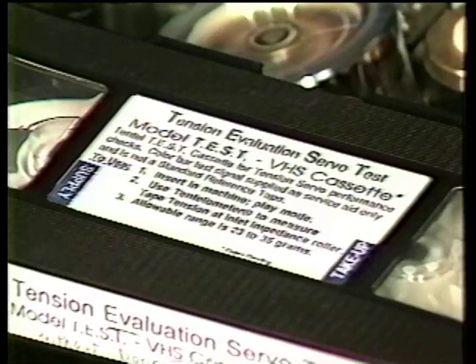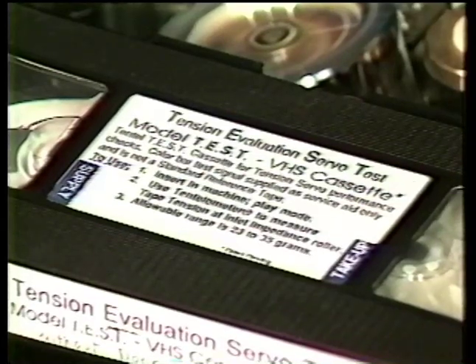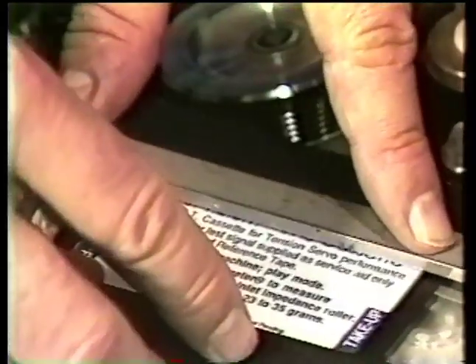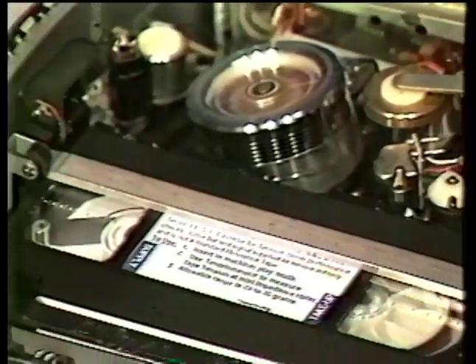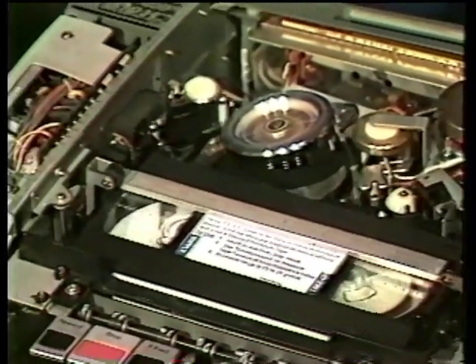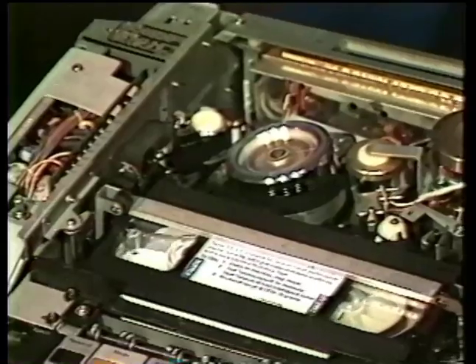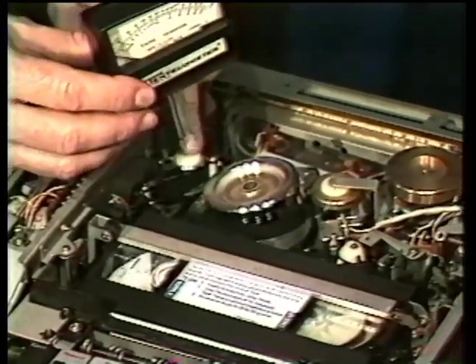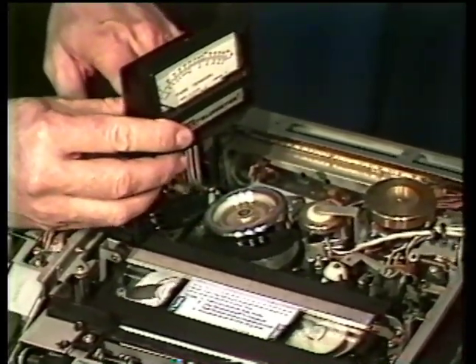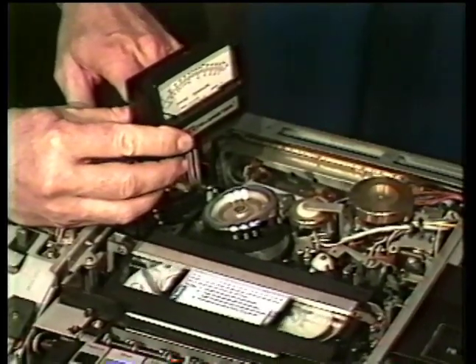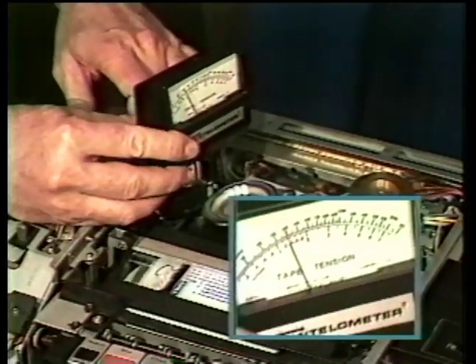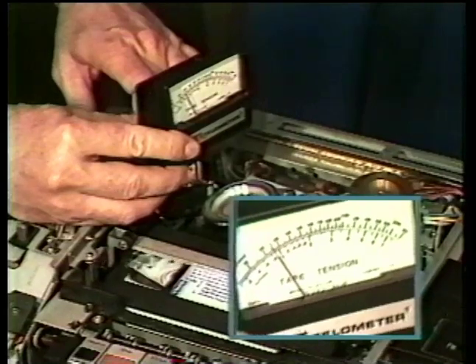Tentel's provided a new test cassette, short for Tension Evaluation Servo Test, to actually check the entire tension servo system of the machine. By inserting the tape into the machine, as you would a cassette, pressing play, each revolution of the supply reel exercises the holdback tension arm throughout its entire range of working. By measuring the tension with the cassette, we want the tension to stay within the 23 to 35 gram standard.